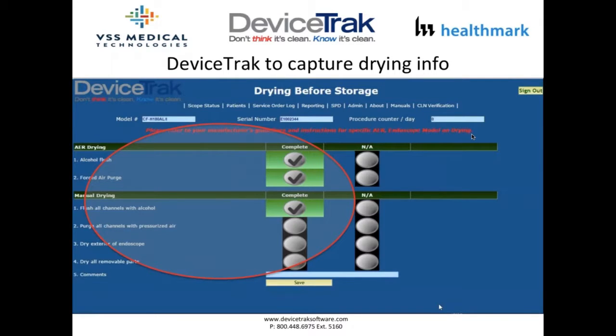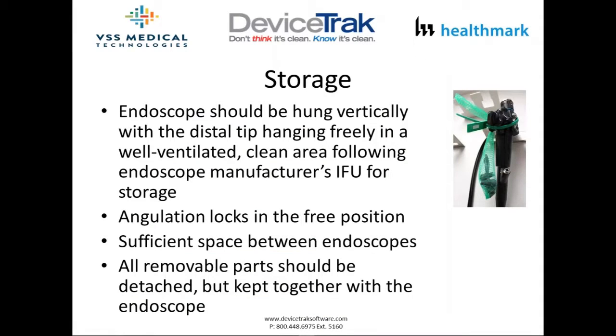DeviceTrak captures this last process before storage, providing options for either automated or manual drying of the endoscope, capturing the alcohol flush and forced air purge through the endoscope.